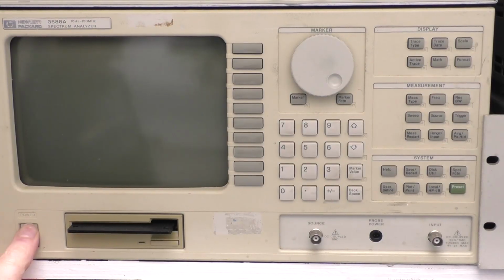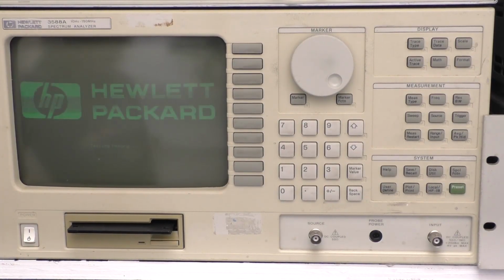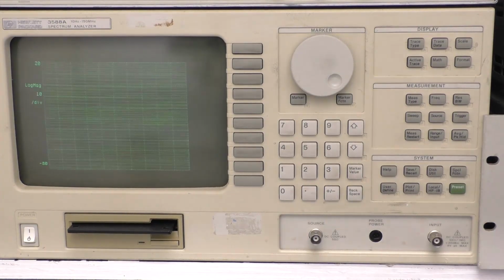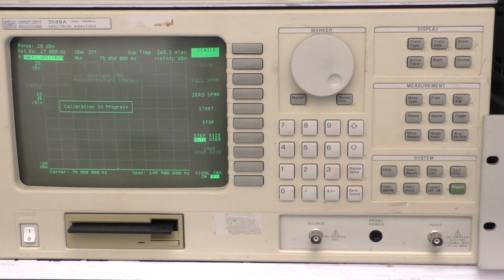Here we will be examining the HP3588A spectrum analyzer. In this clip we will be looking at repairing a unit that has suddenly failed to self-calibrate. Let's fire up the unit. As normal, the unit automatically performs a calibration post-startup. We can see the calibration failure displayed.